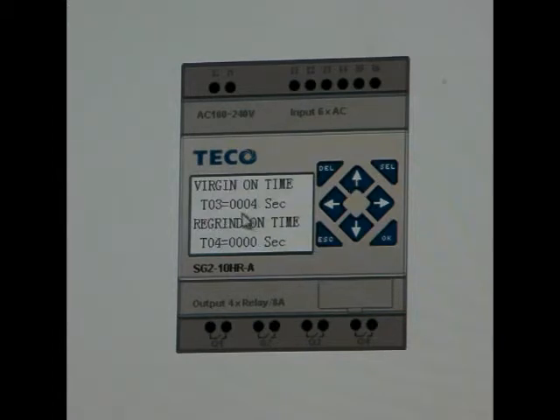Let's say I want to change the virgin on time in this particular loader. The first thing I do is select this operational screen for change. So I'll hit select. You can see there's a highlighted number there, which I can move around to any of the parameters on that screen. I can use the arrow keys just to get to that. Once I get to a digit I want to change, again I will select that. Once I select it, I can change that digit up and down with the arrow keys. When I reach the number or digit that I want, I simply click on OK, and I have made the change. To get out of that mode, I can hit escape.